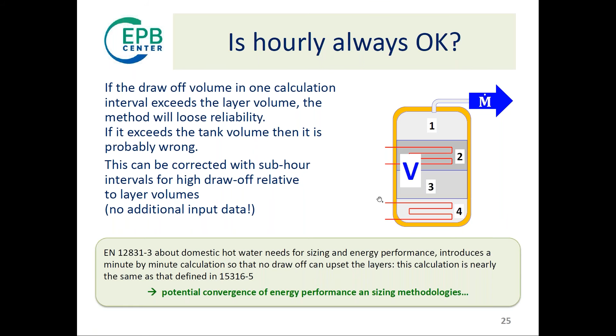Using profiles with a very small time interval is a way to solve this design problem. EN 12831-3, another standard about heating systems in the same series by TC228, does exactly this for the sizing of domestic hot water. The method is quite similar, it's just running on a smaller calculation interval, and they converge easily.